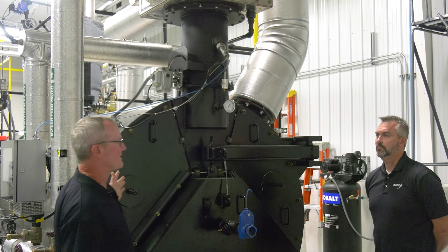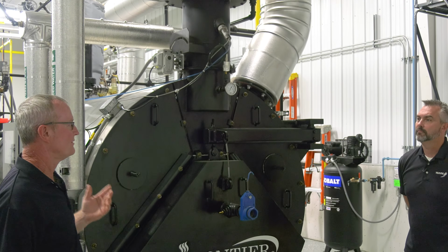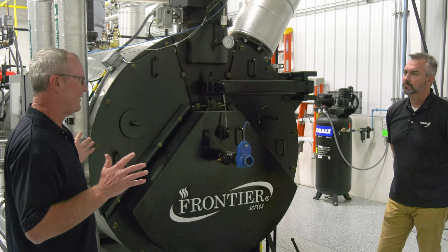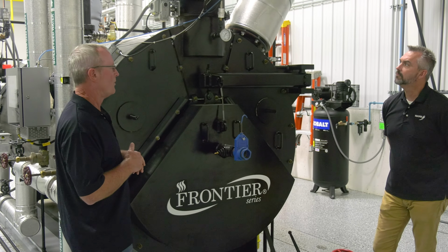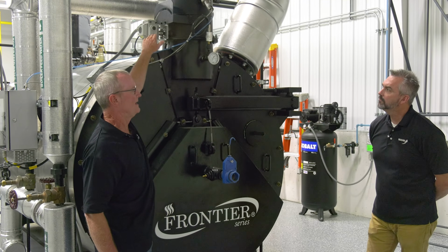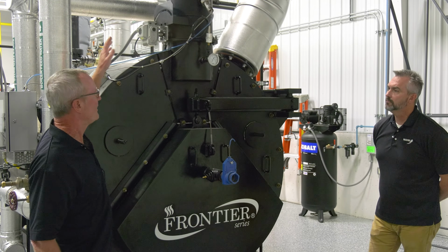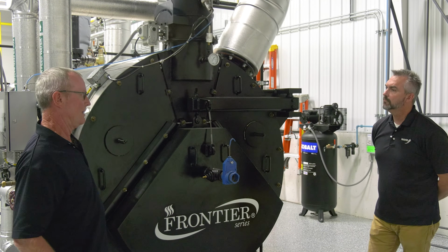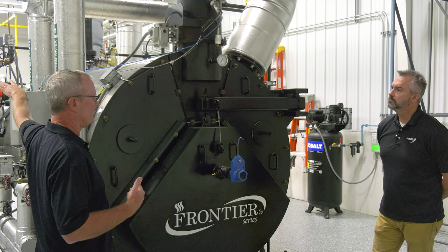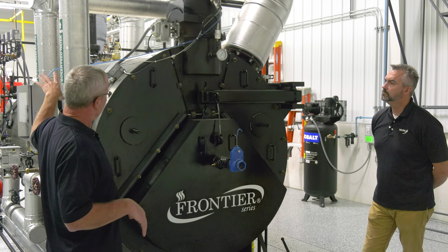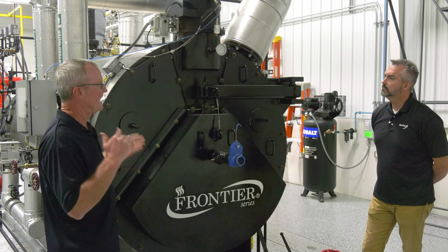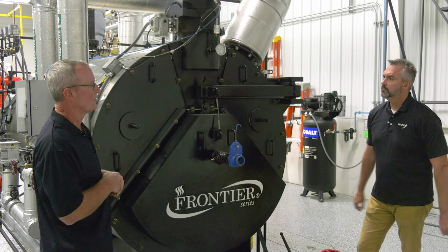That's what we're looking for. That's what the burners are designed for, zero outlet pressure, plus or minus 1/10 of an inch of pressure, which is nothing. The best way to get that is to put a modulating damper on there. Then we can control that. That is set up when we do the initial combustion commissioning. We'll set that damper up along with the servos on the gas and the air pushing into the boiler to maintain that zero that we're looking for coming out of that boiler.